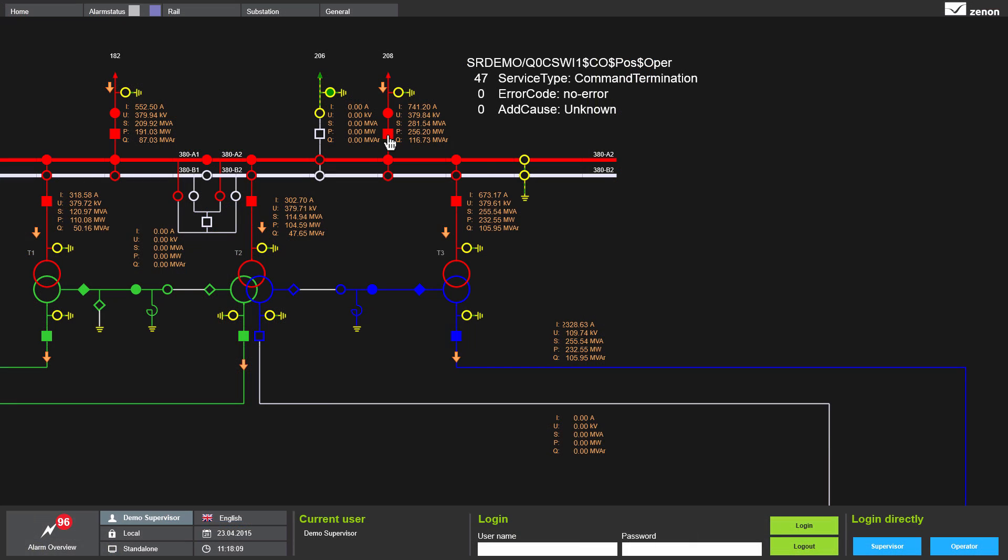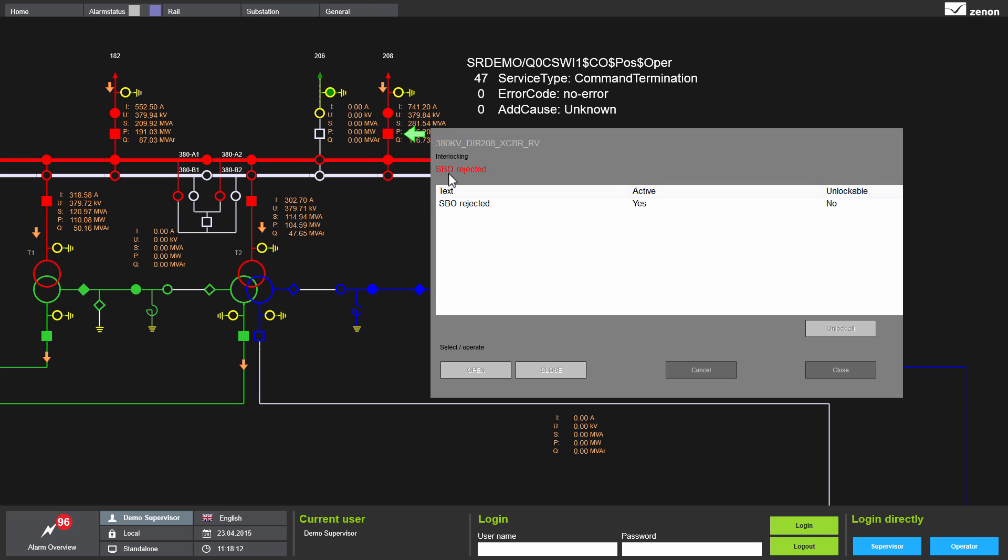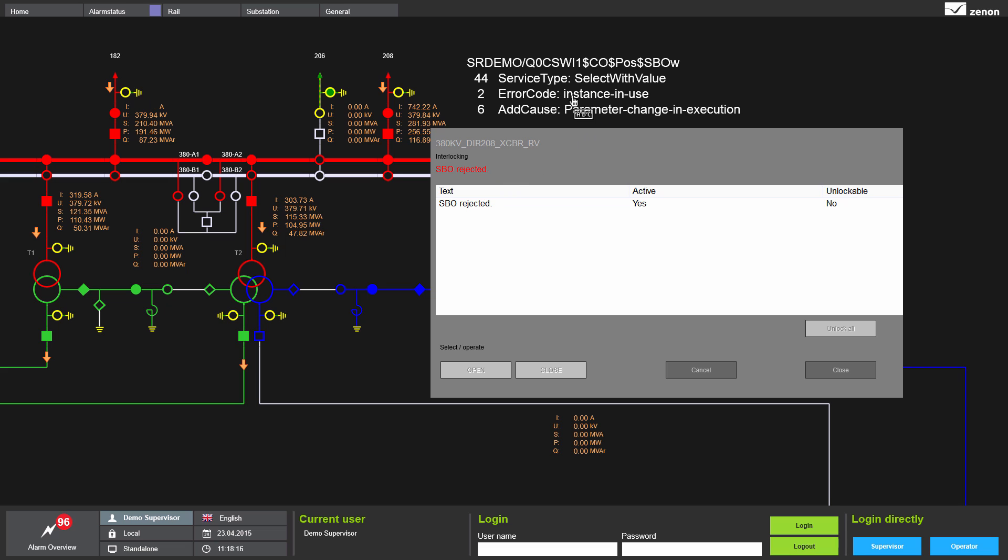Now I want to switch off the circuit breaker. In the command processing screen, you will see the information: SBO, select before operate, rejected. This is a system interlocking and thus prevents the user from confirming the action.